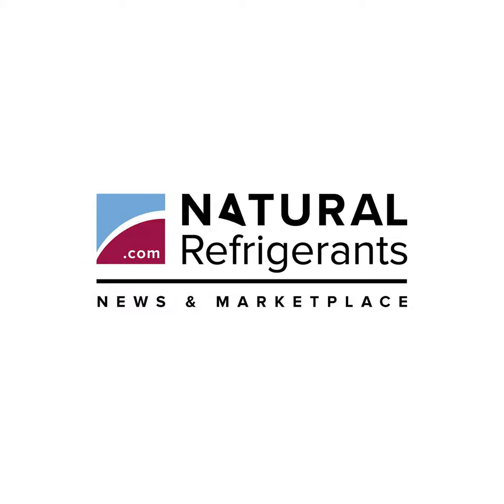Rotary compressors exhibit excellent performance comparable to scroll, he added. To further optimize R290 rotary compressor performance, the company has developed new oil return structures that cut the oil carryover rate, OCR, to below 1%. Previously, the OCR exceeded 3%, which reduced heat exchanger efficiency, Yi noted.